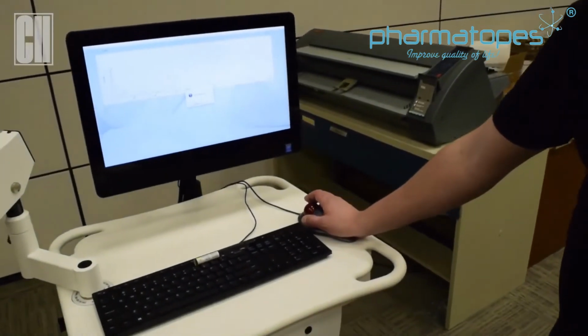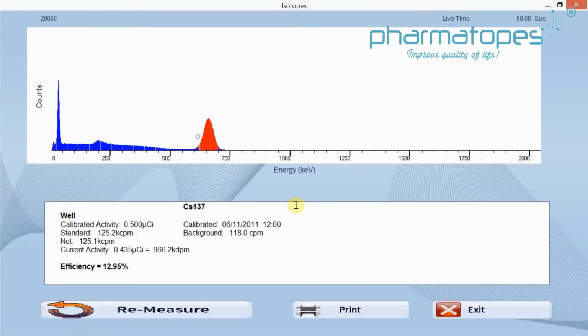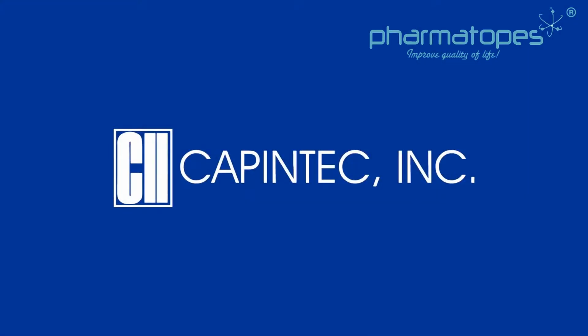Once the cesium has completed its counting, click on yes to accept the measurement, and you'll see a result for your efficiency. For the well detector, you should see an efficiency of 8.3 to 16.6 as an expected value. So once you're within limits, that would be your current efficiency for cesium on the well detector. Once that is done, you can then exit.